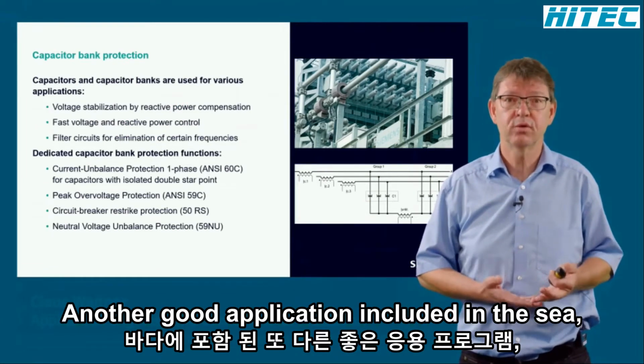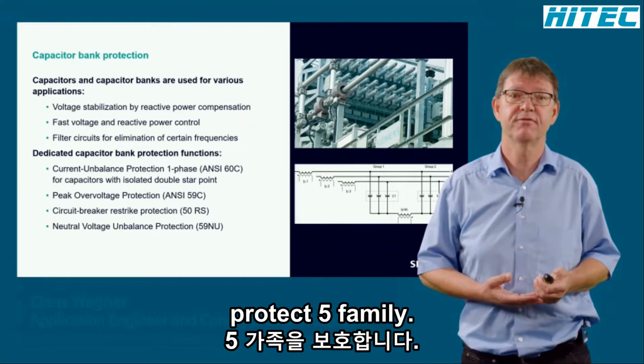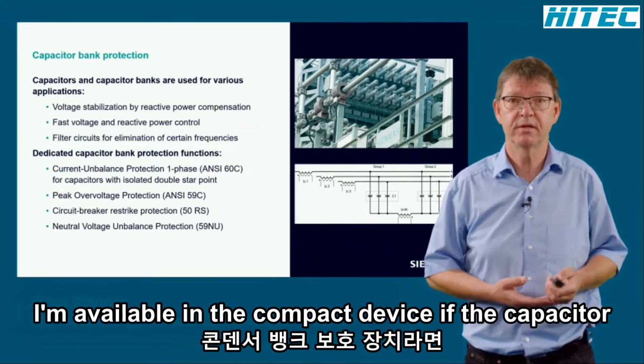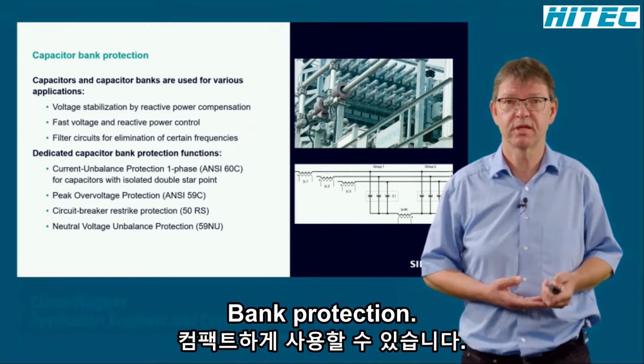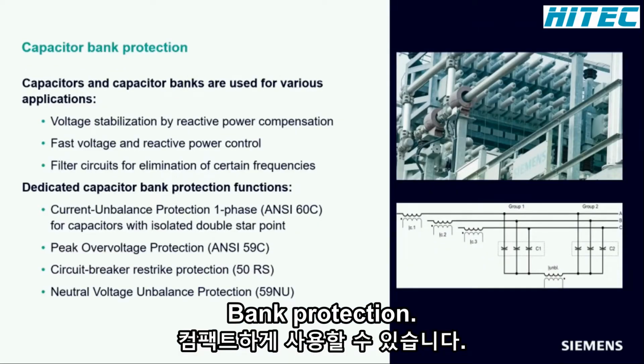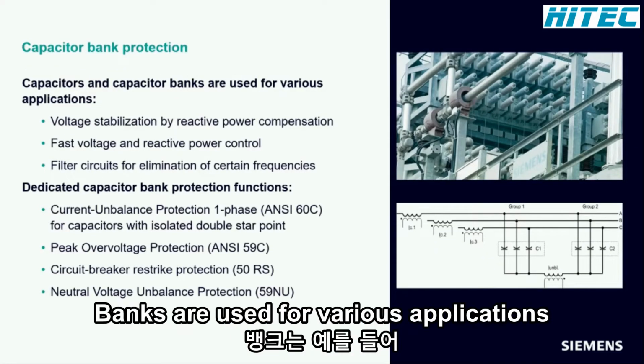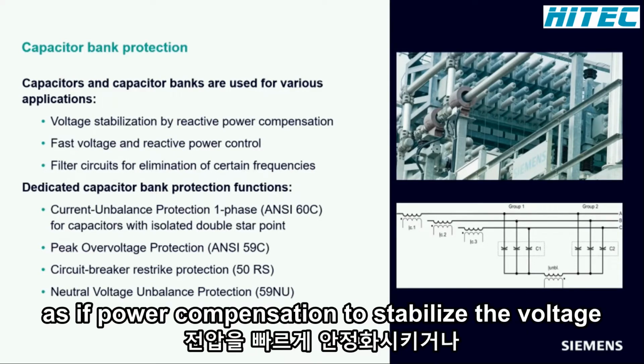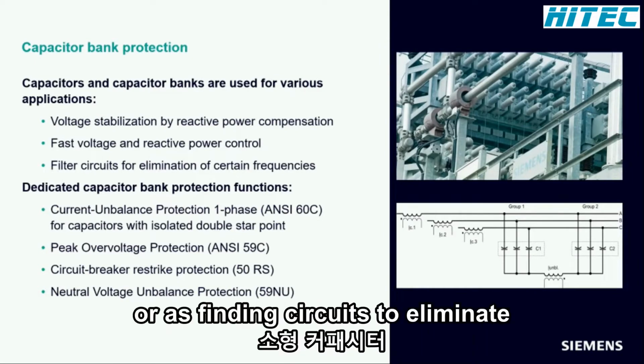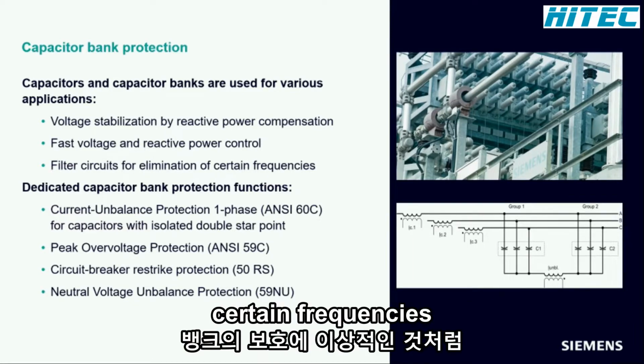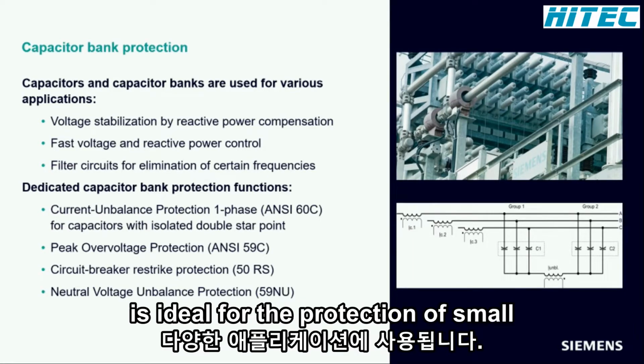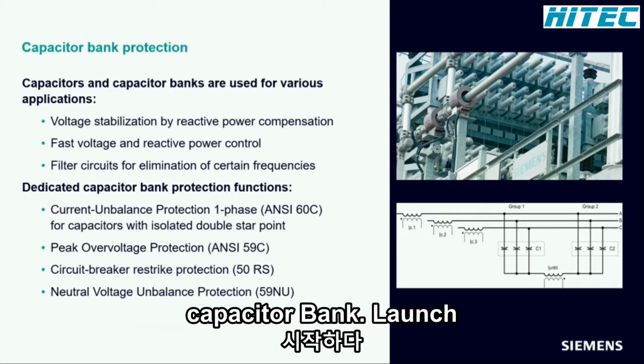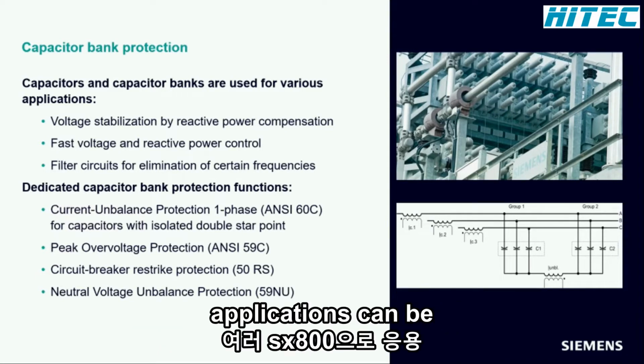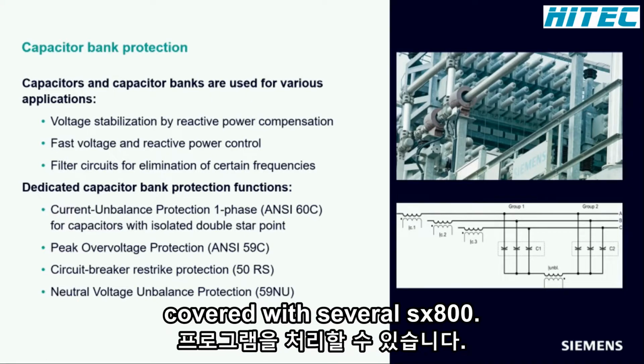Another good application included in the SIPROTEC 5 family and available in the compact device is the capacitor bank protection. Capacitors and capacitor banks are used for various applications, for example, as reactive power compensation to stabilize the voltage, as fast voltage and reactive power control, or as filter circuits to eliminate certain frequencies. The 7SX800 is ideal for the protection of small capacitor banks. Larger applications can be covered with several SX800.